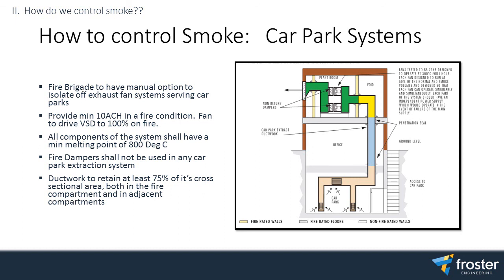Car park systems. It's an interesting one. So for car parks, we need to have, on a signal, fan drives to 100%. Again, you have to give the fire brigade the option of isolating it, shutting it off. All the ductwork systems, everything has to be rated to this condition, so there's no failure of that extraction path. And same as kitchen, you can't have any fire dampers in the escape path or the exhaust path. This is going to be an interesting one in 5, 10, 15 years when electric cars are common. It's probably still a bit working off this old standard.